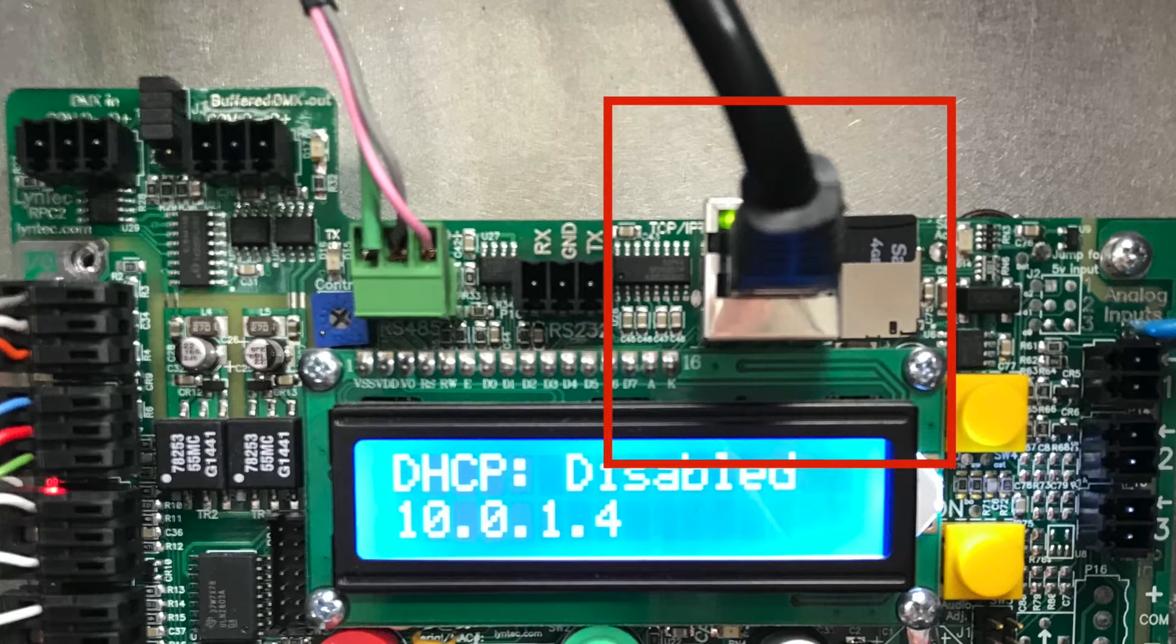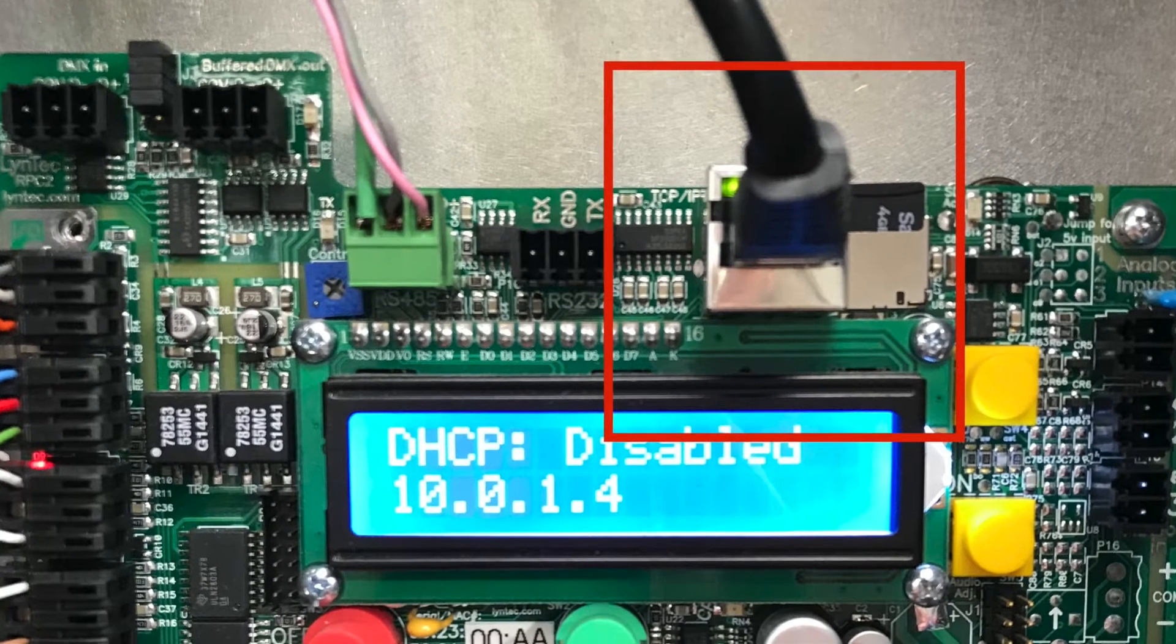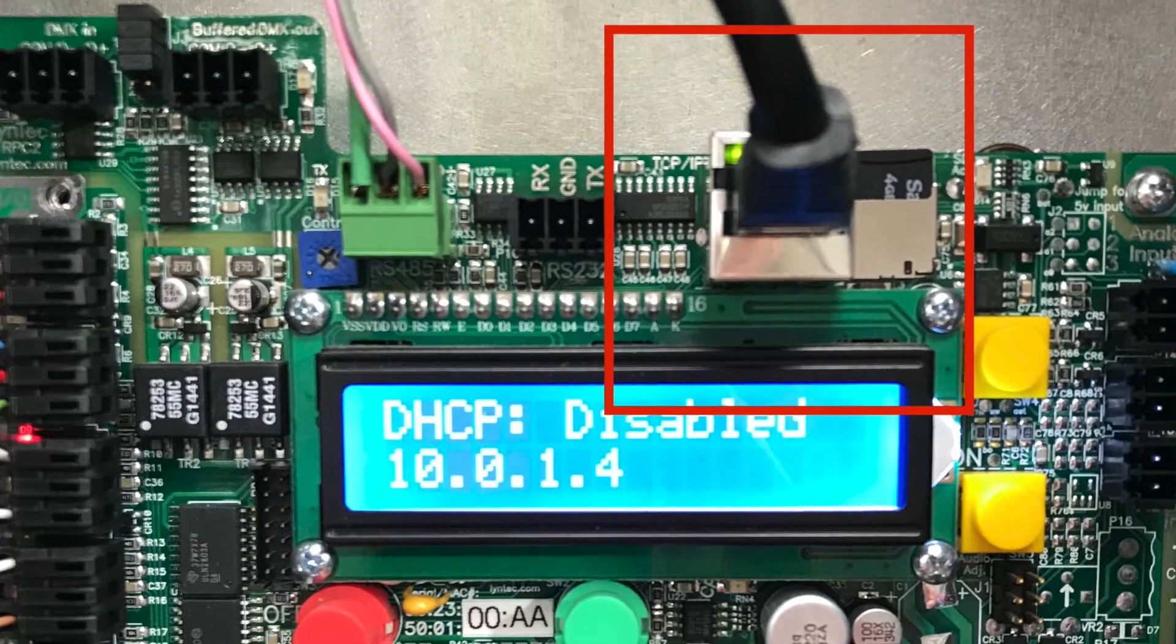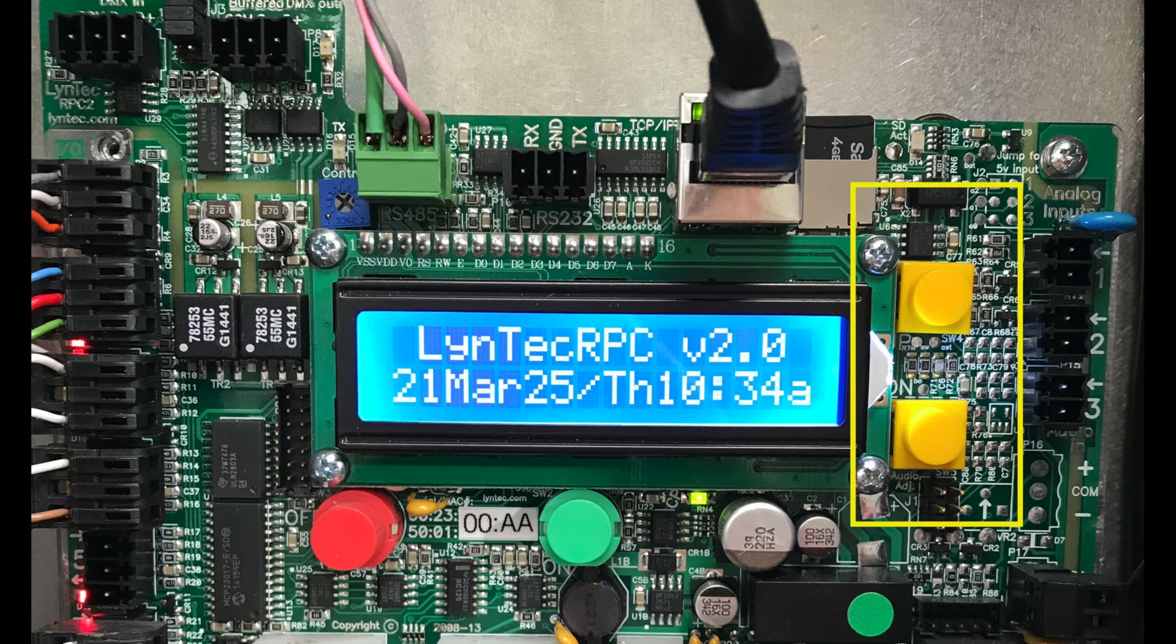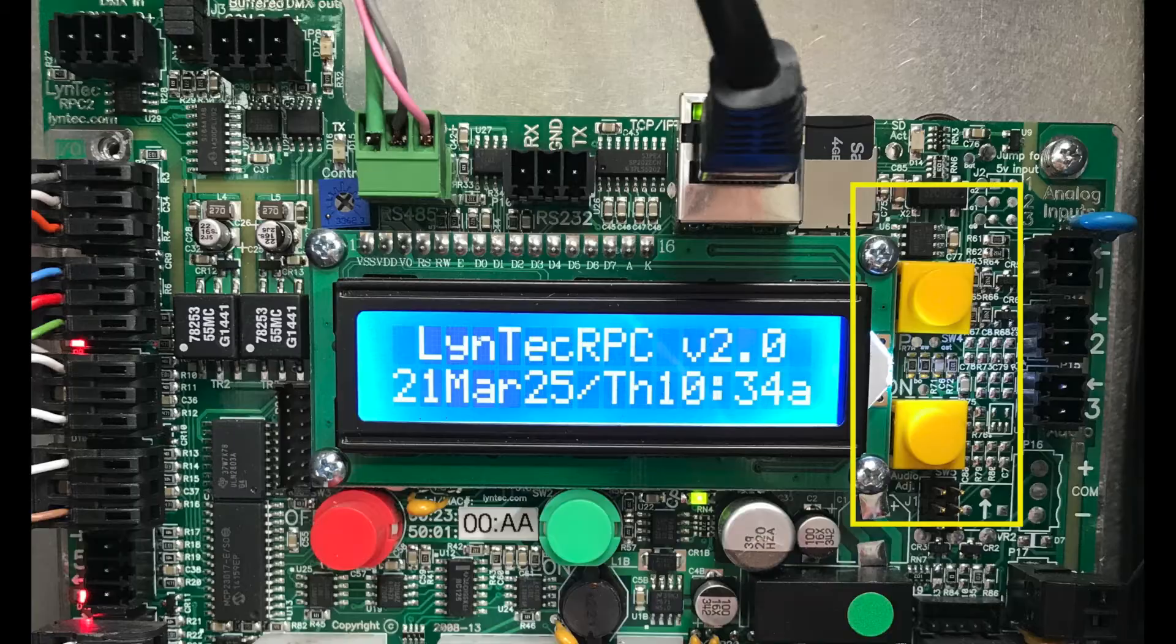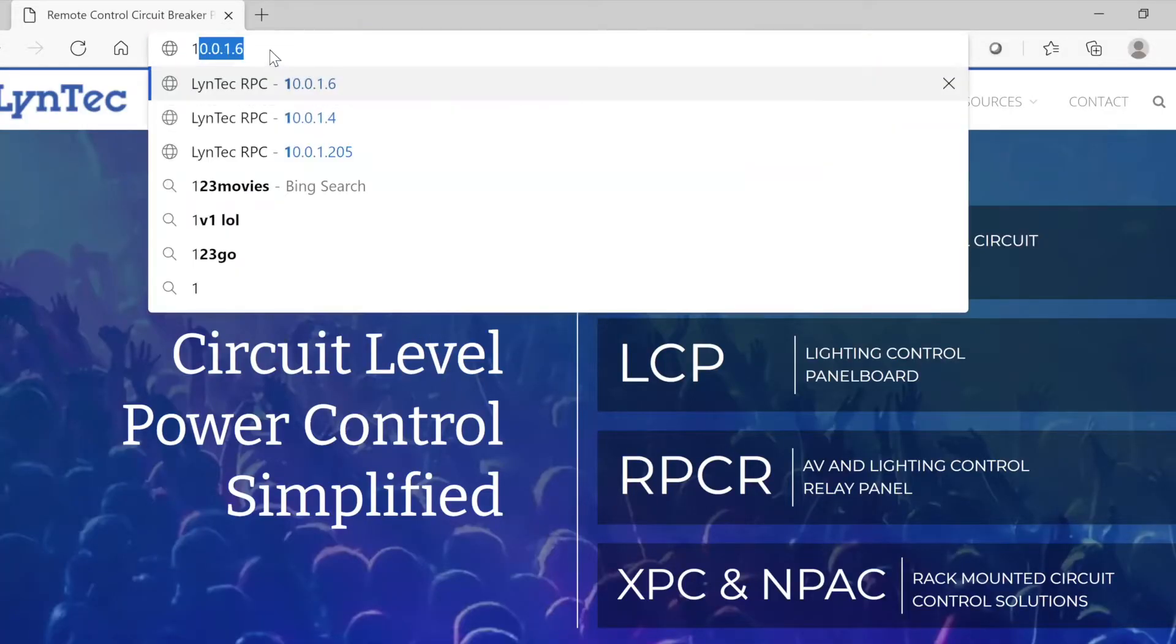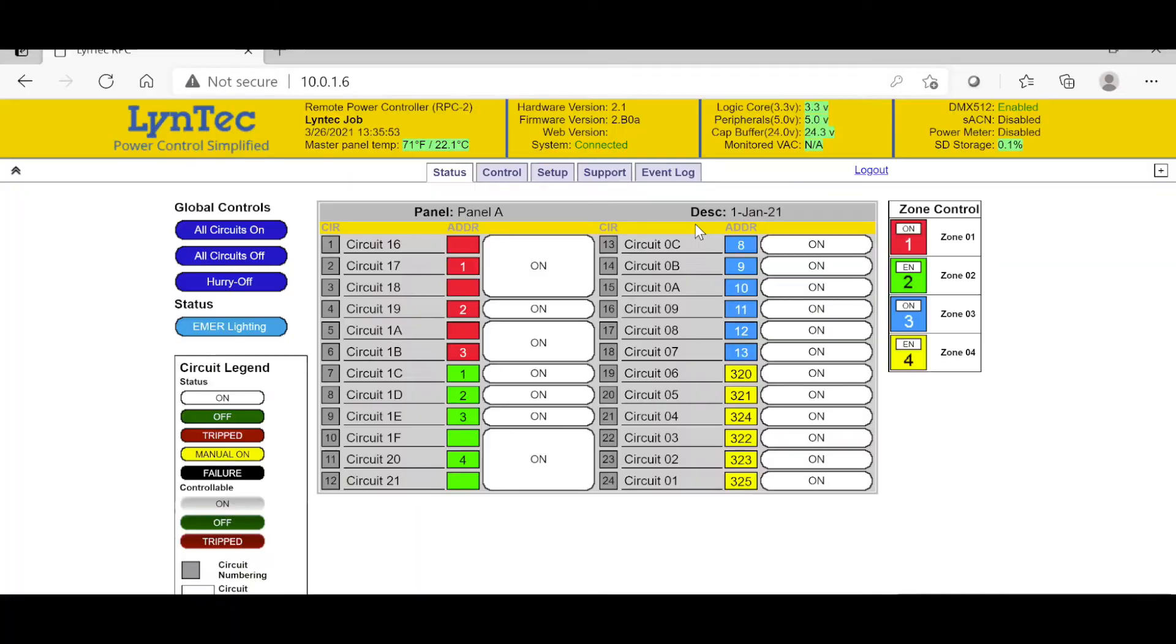After connecting to the RPC controller with the standard network cable plugged into the Ethernet port, push the top yellow button twice to display the IP address and enter it into any internet-based web browser. Default login credentials for the username are admin and the default password is PW. You can change these momentarily.